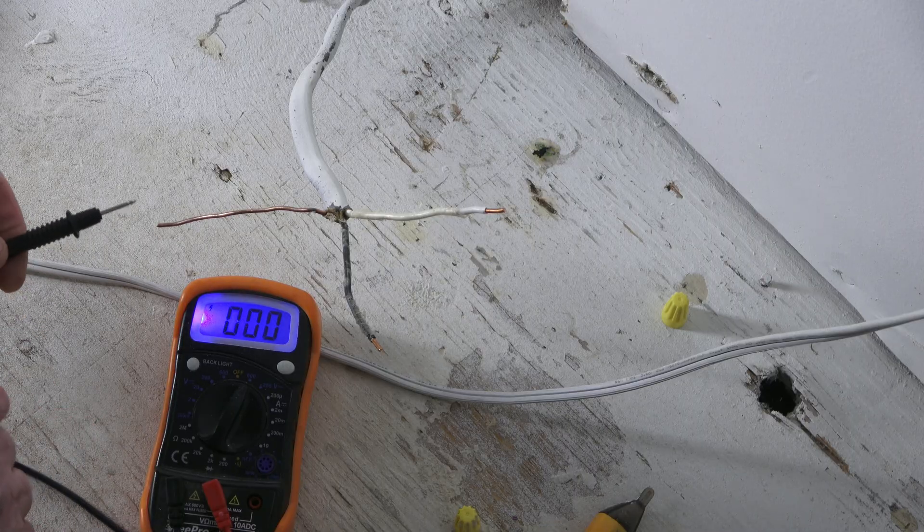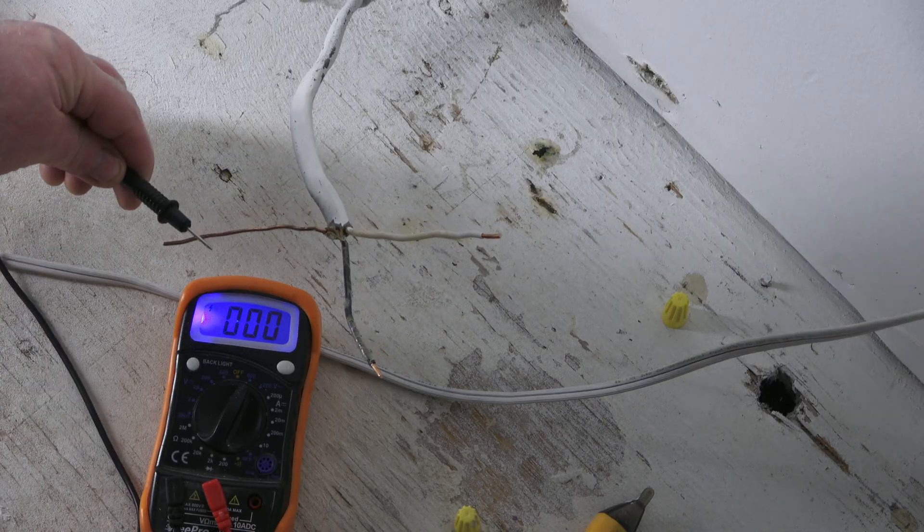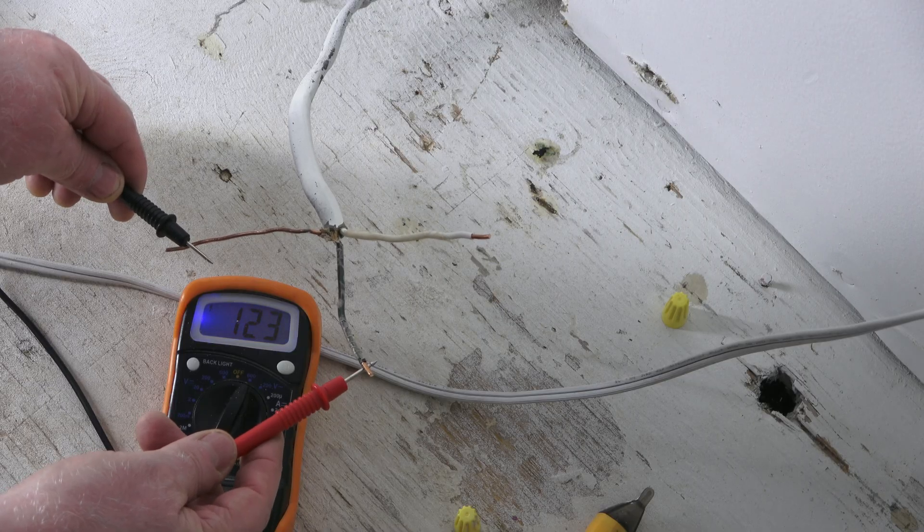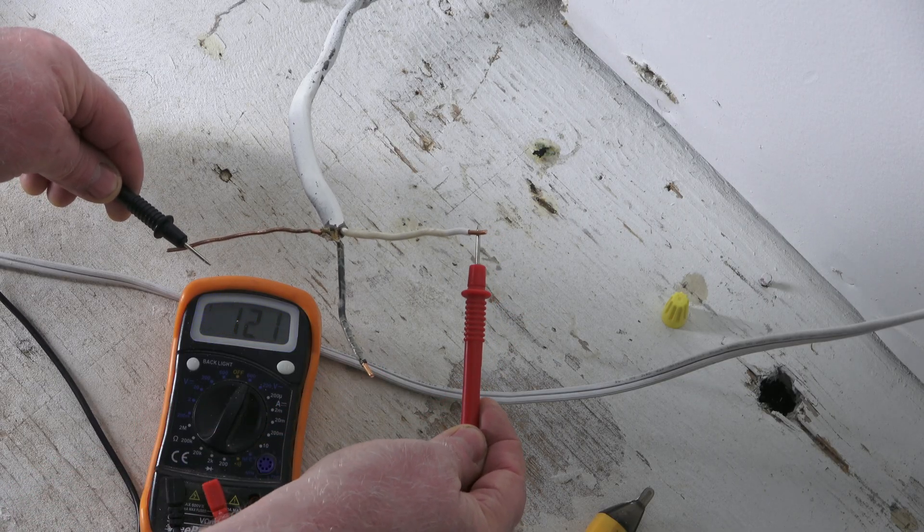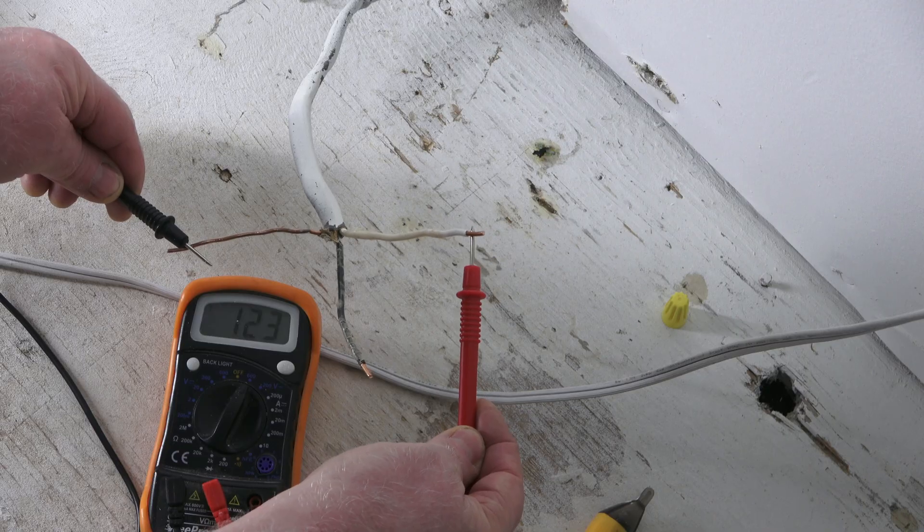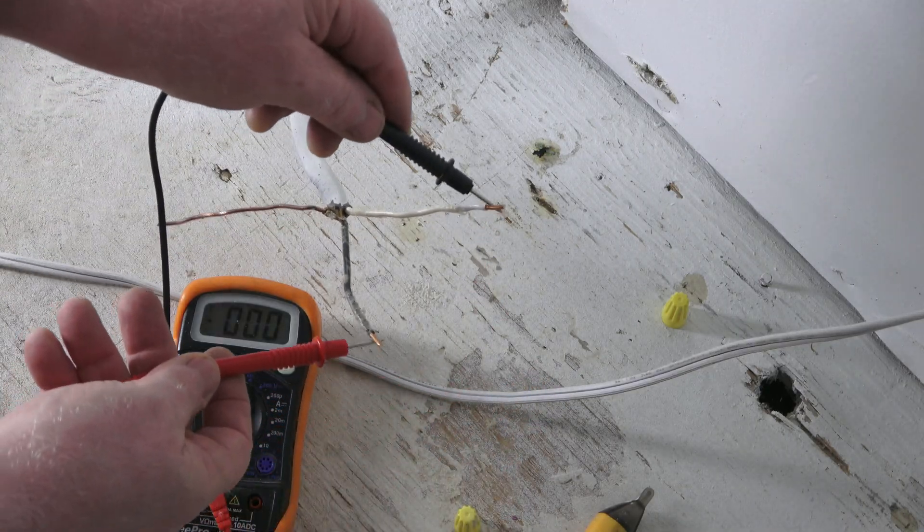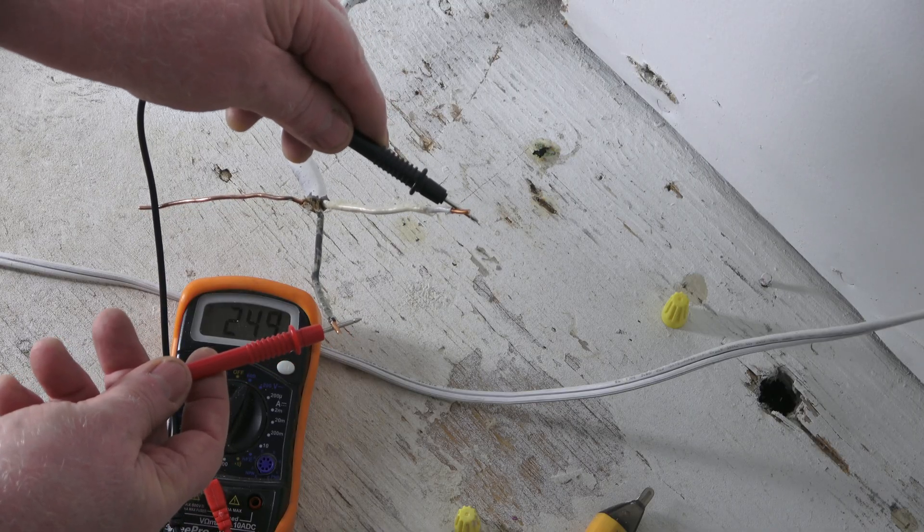So when checking with the meter, go to ground, one leg, 123 volts, then check your other one, 123. Perfect. Then when you check between these two, it should be 240, 248, 249. All right.